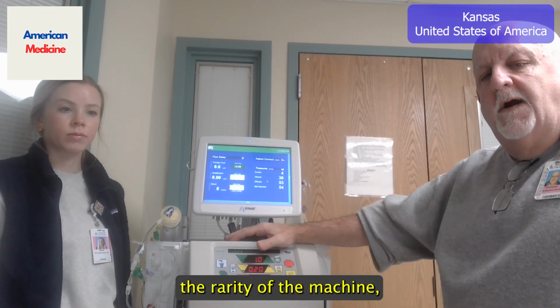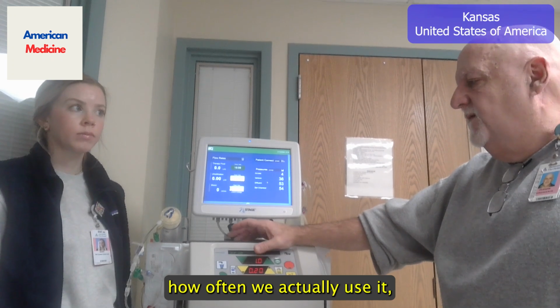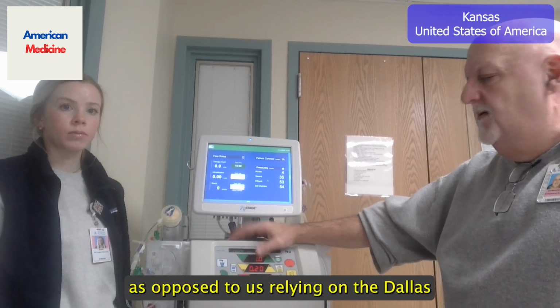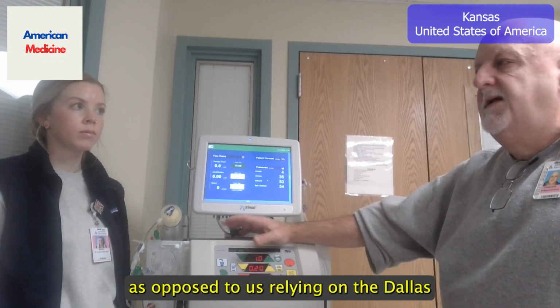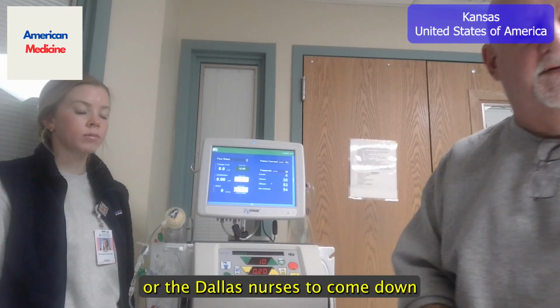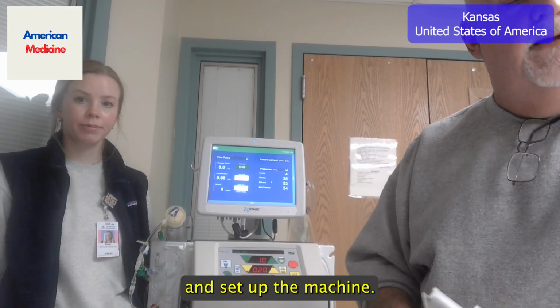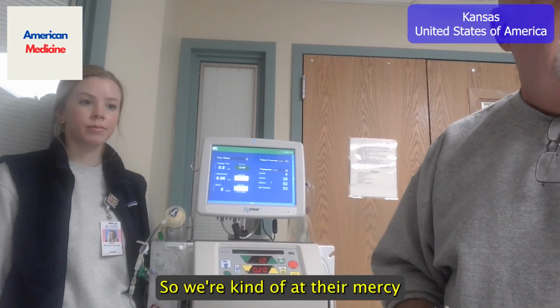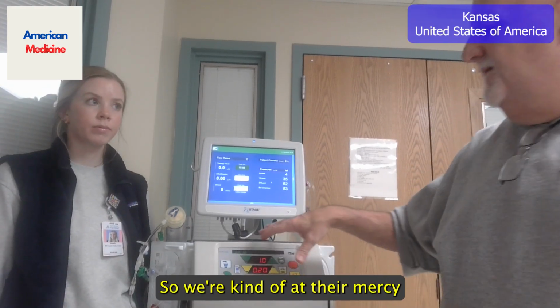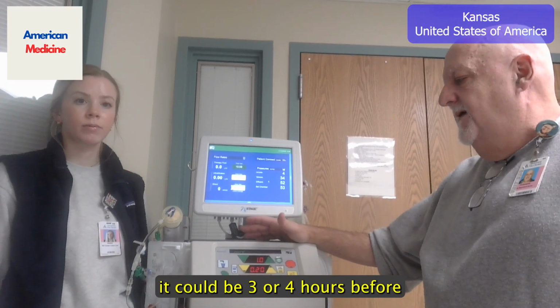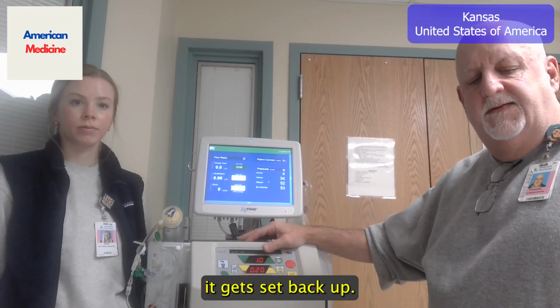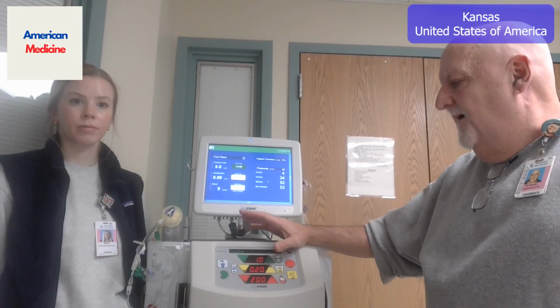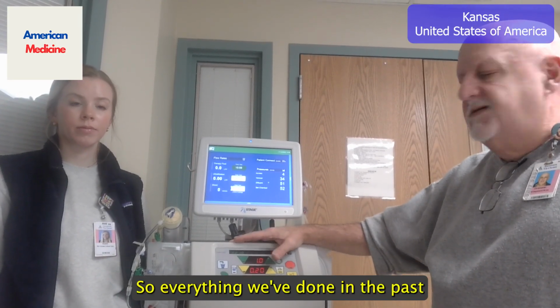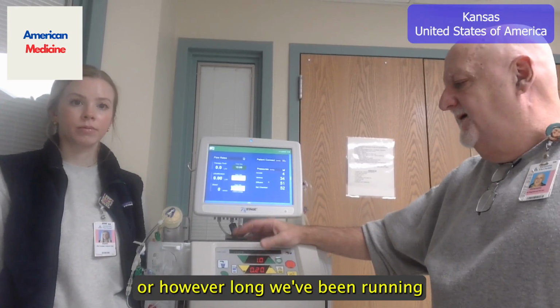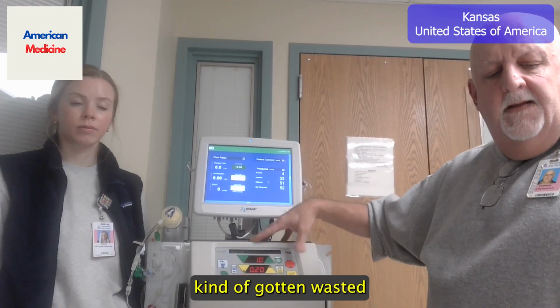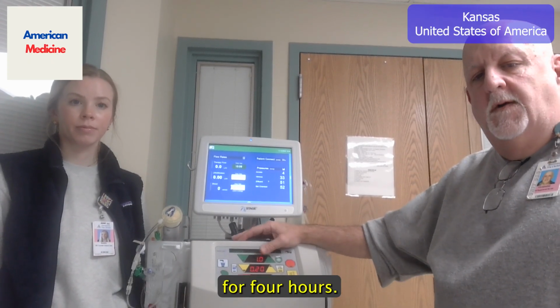It's just the rarity of this machine and how often we actually use it, as opposed to us relying on the dialysis machine or the dialysis nurses to come down and set up the machine. So we're kind of at their mercy. If it goes down in the middle of the night, it could be 3 or 4 hours before it gets set back up. So everything we've done in the past 12 hours or however long we've been running kind of gets wasted just because this machine goes down for 4 hours.